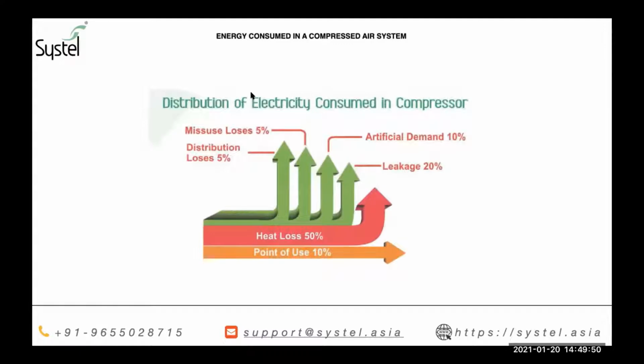You should be aware that compressed air is one of the most inefficient utilities available to the industry, with hardly 10% to 20% of the actual input energy getting into a usable form and reaching the point of use. There are multiple losses in a compressed air system, with heat being the biggest, usually 40 to 50% of energy lost. Leakages, artificial demand, misuse, and distribution losses usually contribute somewhere between 15 to 20%. So out of the 100% electricity fed into a compressor, hardly 20% gets converted and reaches the actual point of use.